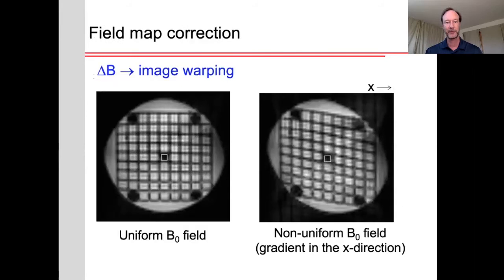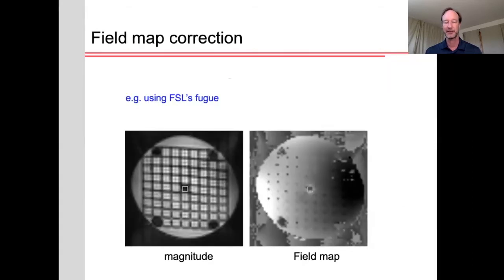Here's an example of a phantom with a plastic grid inside of it, where we've applied some non-uniformity in the x-direction, you can see that the image is distorted. However, if we acquire a separate field map, then we can use that field map to correct for these distortions, for example using FSL's FUGUE.